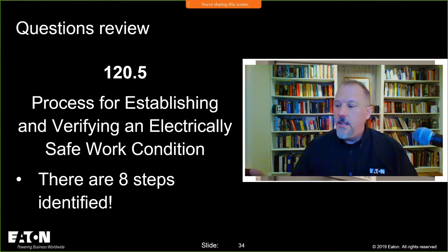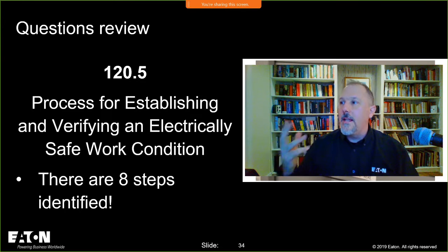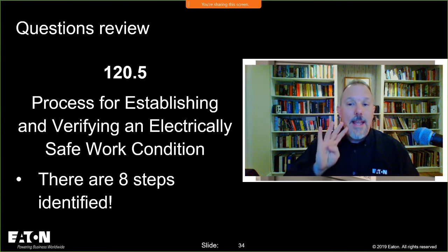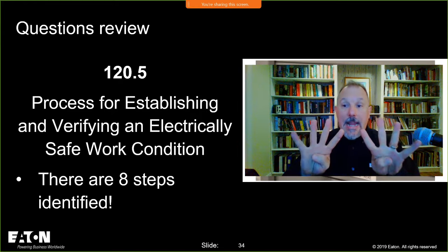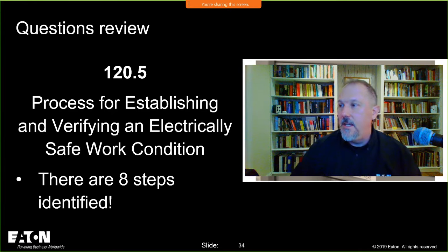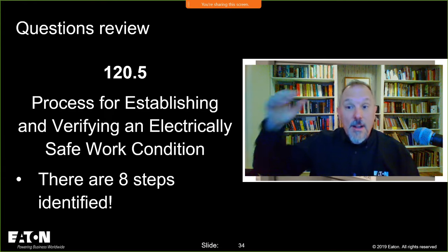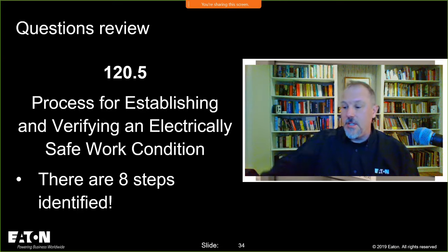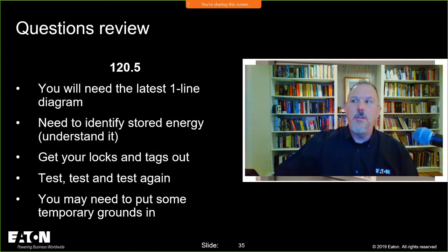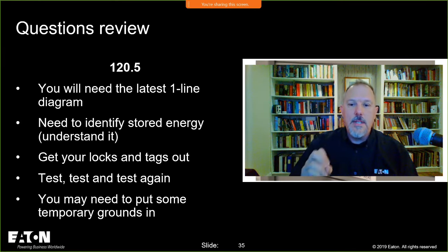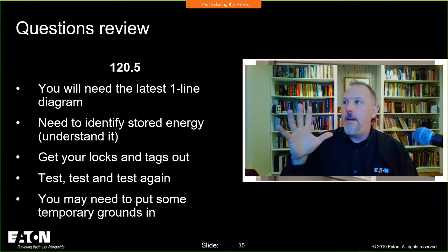120.5 in 70E talks about the process for establishing and verifying an electrically safe work condition. There are eight steps identified. It's an 8-step process to establish an electrically safe work condition; there are eight things that you need to think about. You need to make sure you have that latest one-line diagram. It is critical. I can't say that enough.